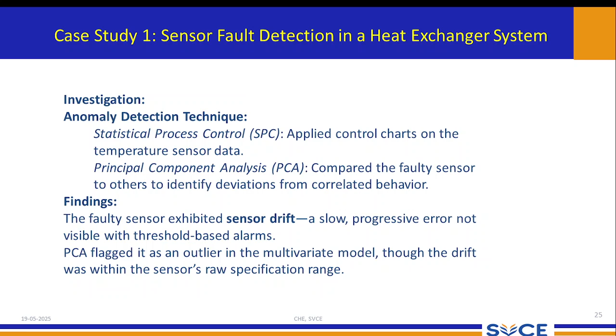And the corrective action, what they did: the sensor was recalibrated. They identified the problem with the sensor, and it was recalibrated. Despite it showing 58 degrees when the actual temperature was 60 degrees, there was a sensor problem. So a redundant sensor and an anomaly detection alert were added to the system.